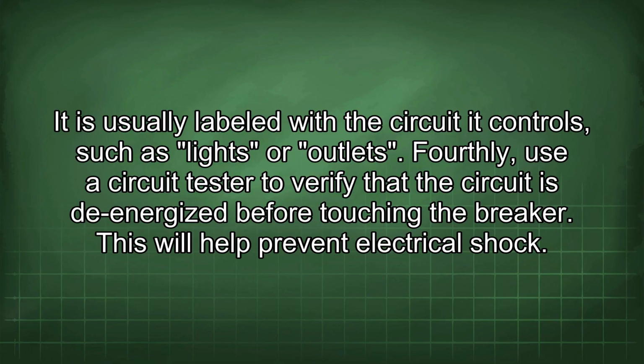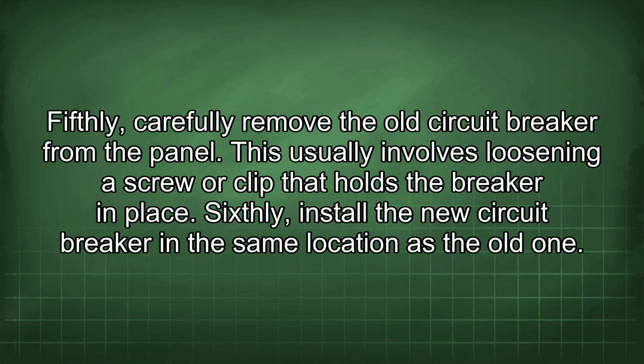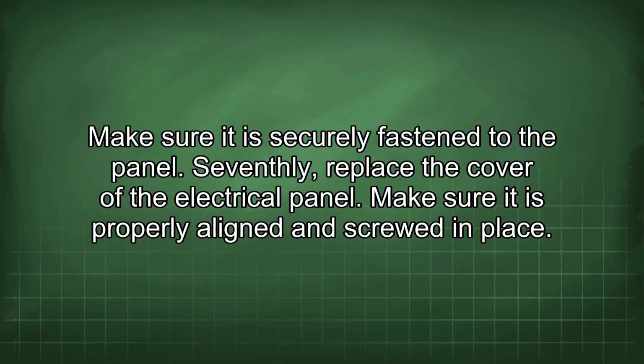Fourthly, use the circuit tester to verify that the circuit is de-energized before touching the breaker. This will help prevent electrical shock. Fifthly, carefully remove the old circuit breaker from the panel. This usually involves loosening a screw or clip that holds the breaker in place. Sixthly, install the new circuit breaker in the same location as the old one. Make sure it is securely fastened to the panel. Seventhly, replace the cover of the electrical panel. Make sure it is properly aligned and screwed in place.